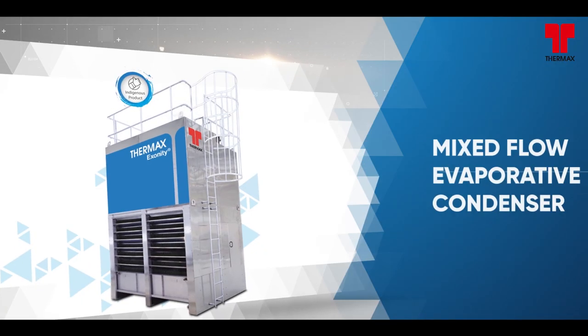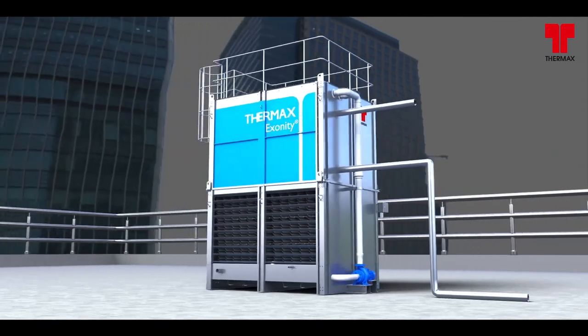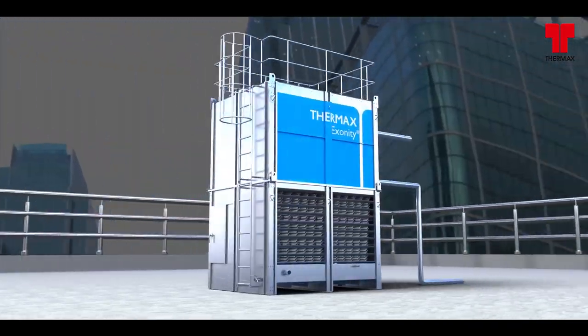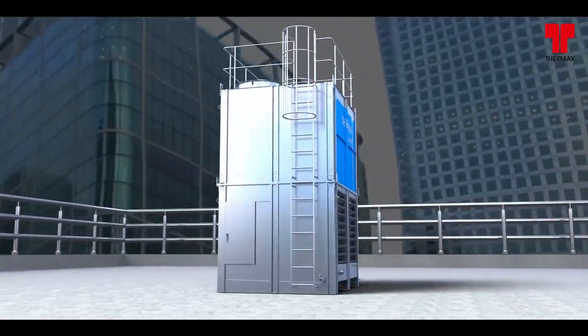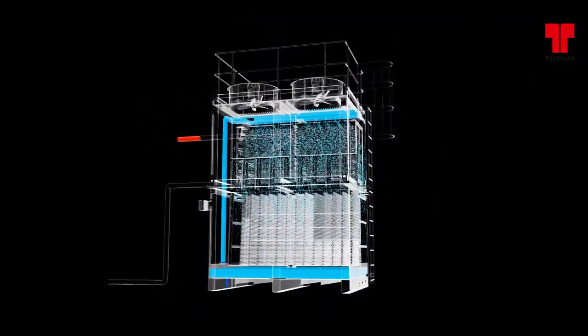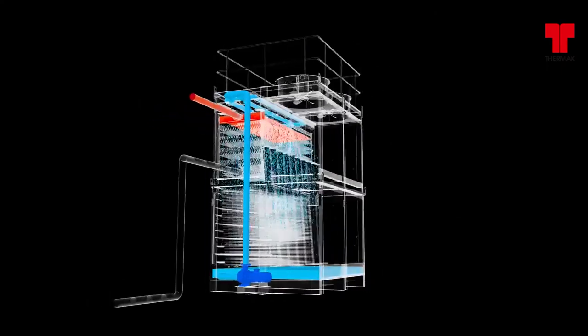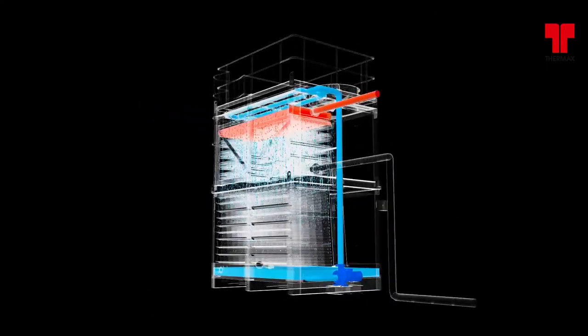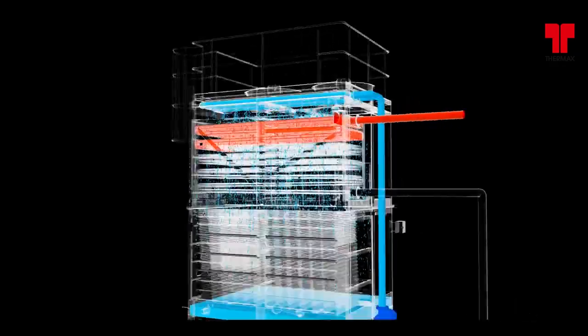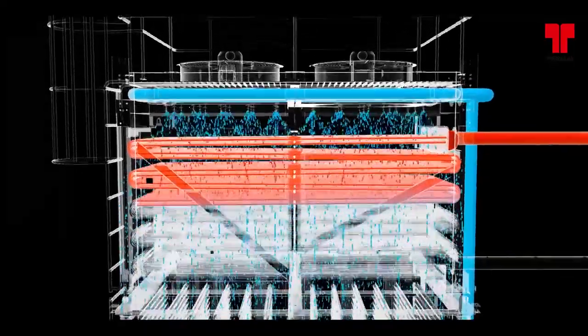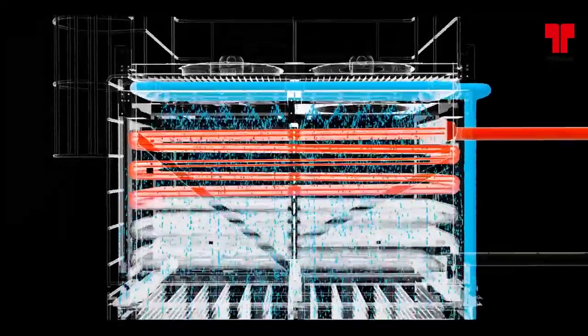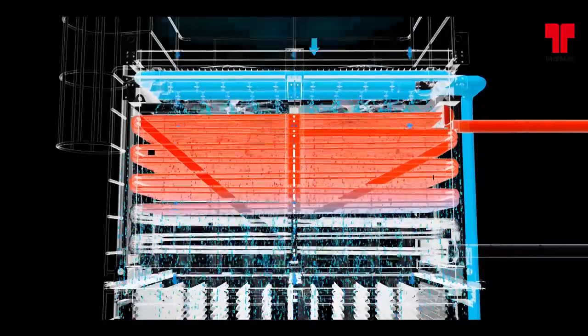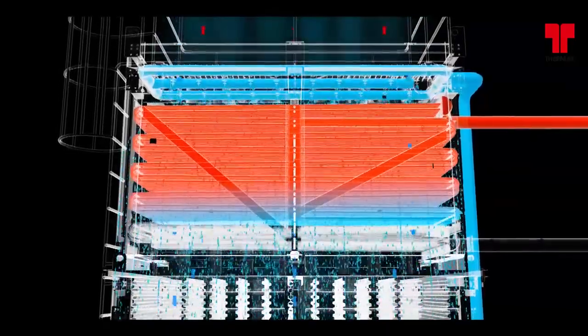Mixed flow EVC. In this type of EVC, the refrigerant is circulated through the coil of the evaporative condenser. Heat from the refrigerant is dissipated through the coil tubes. The heat is removed directly by the downward natural induced air, aided by a spray of water cascading over the tubes.